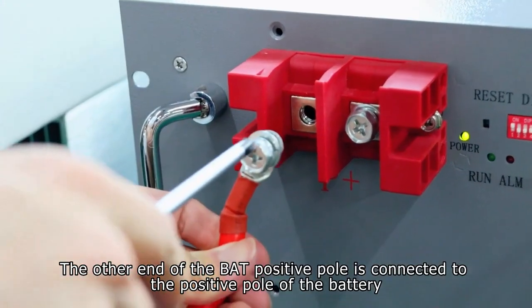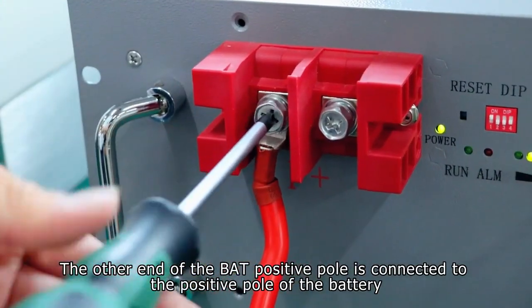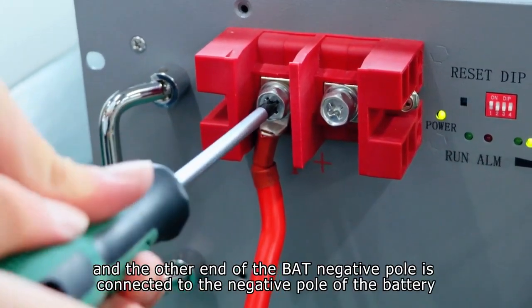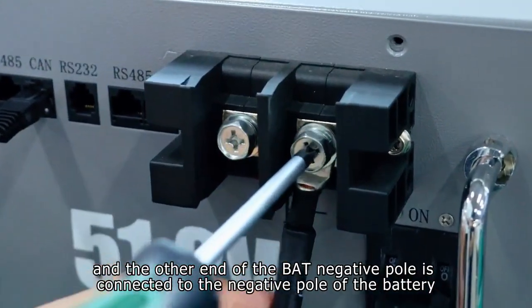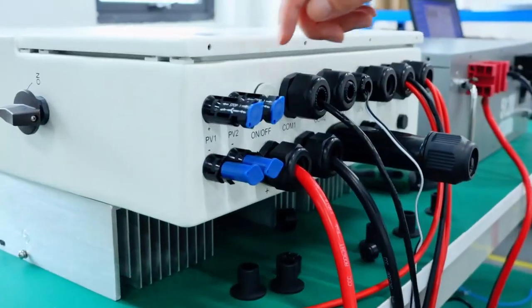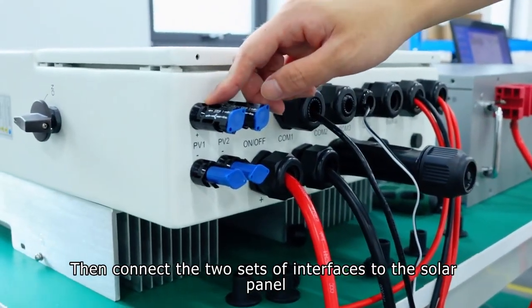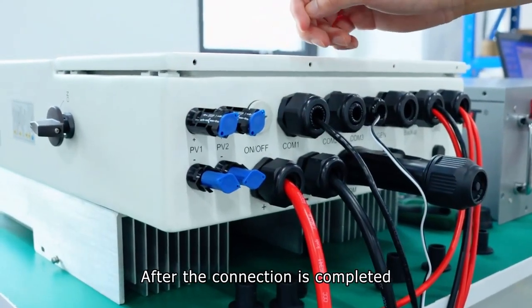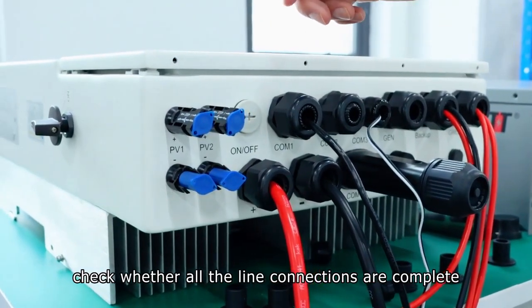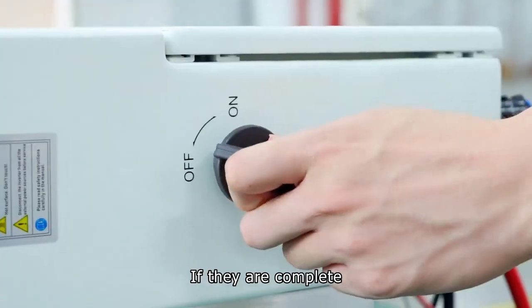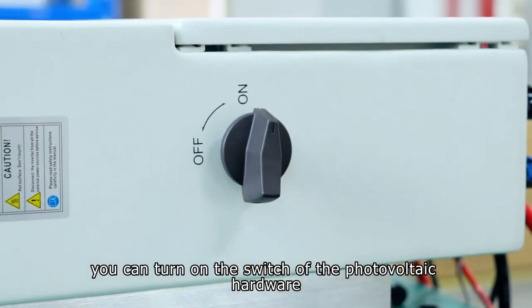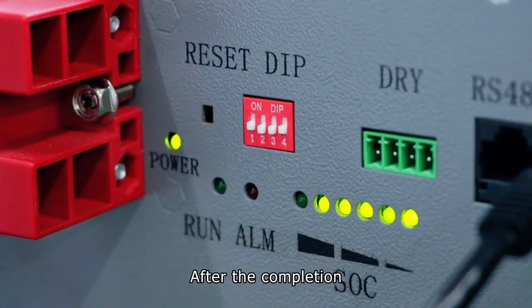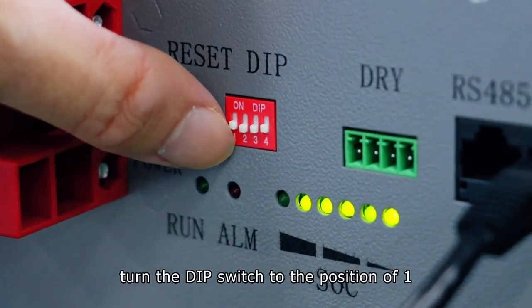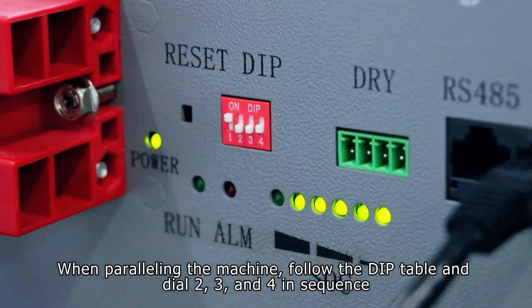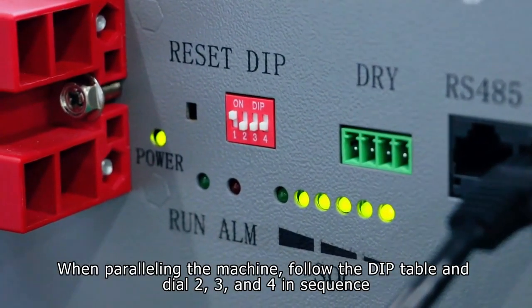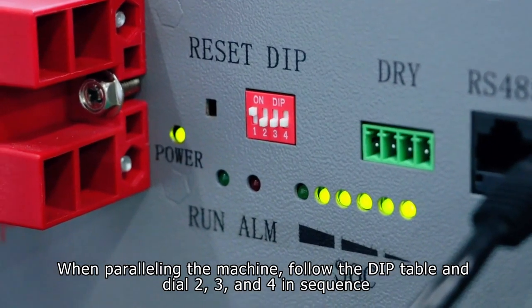The other end of the BAT positive pole is connected to the positive pole of the battery, and the other end of the BAT negative pole is connected to the negative pole of the battery. Then connect the two sets of interfaces to the solar panel. After the connection is completed, check whether all the line connections are complete. If they are complete, you can turn on the switch of the photovoltaic hardware. After the completion, turn the dip switch to the position of 1. When paralleling the machine, follow the dip table and dial 2, 3, and 4 in sequence.